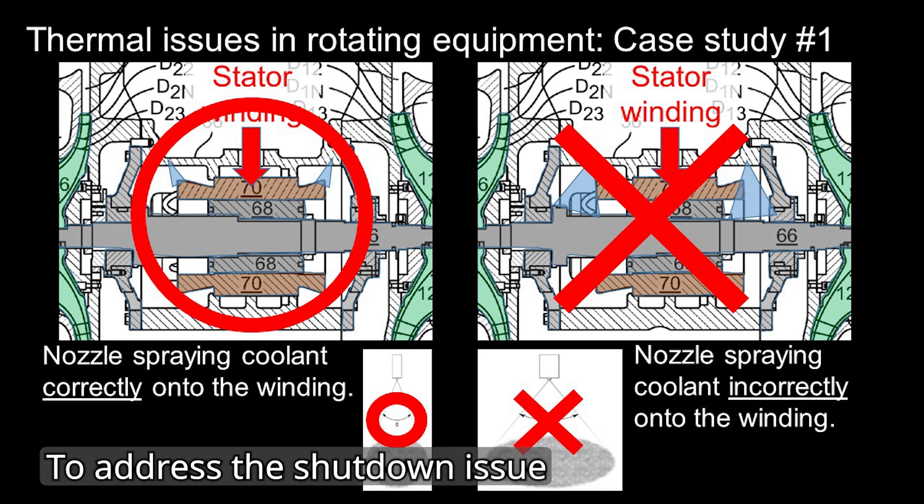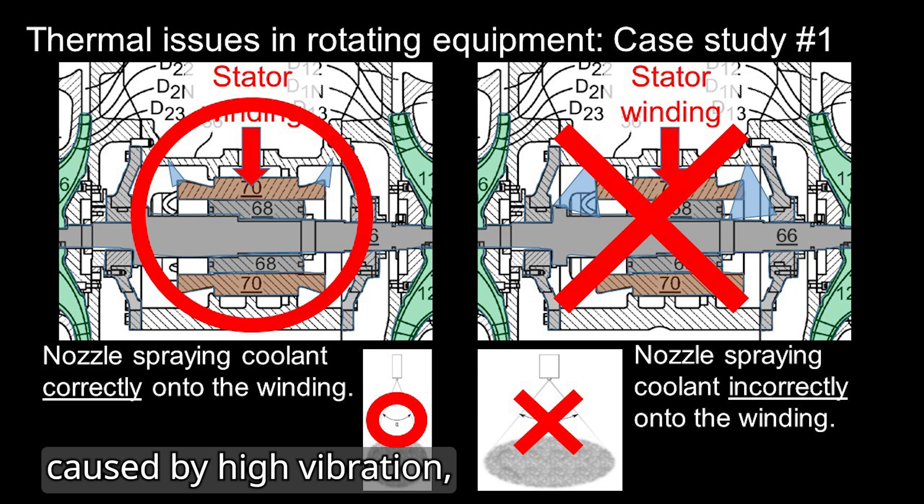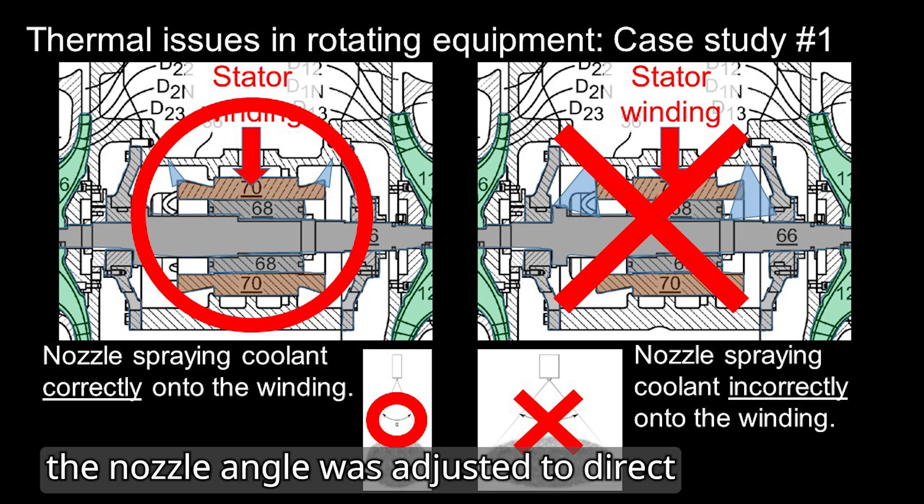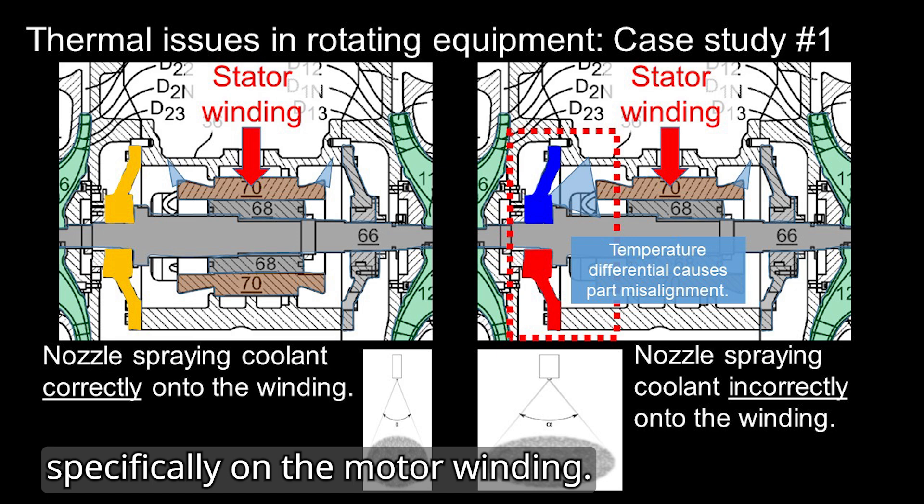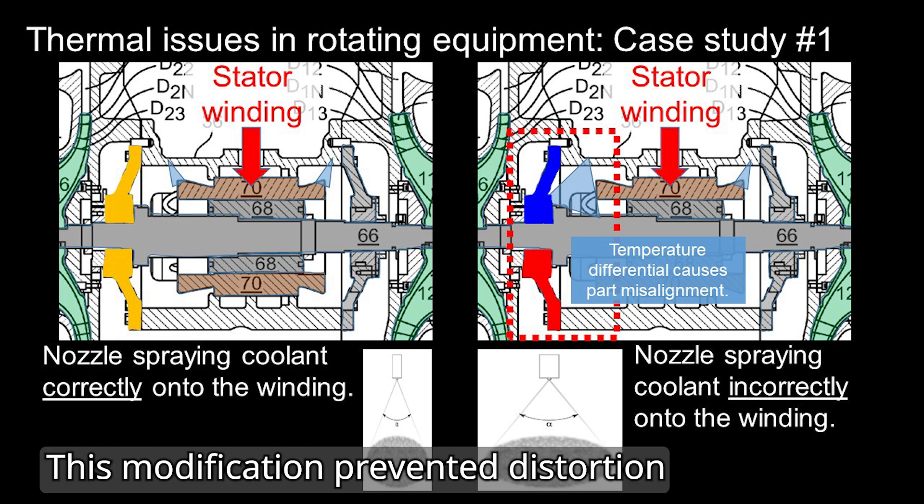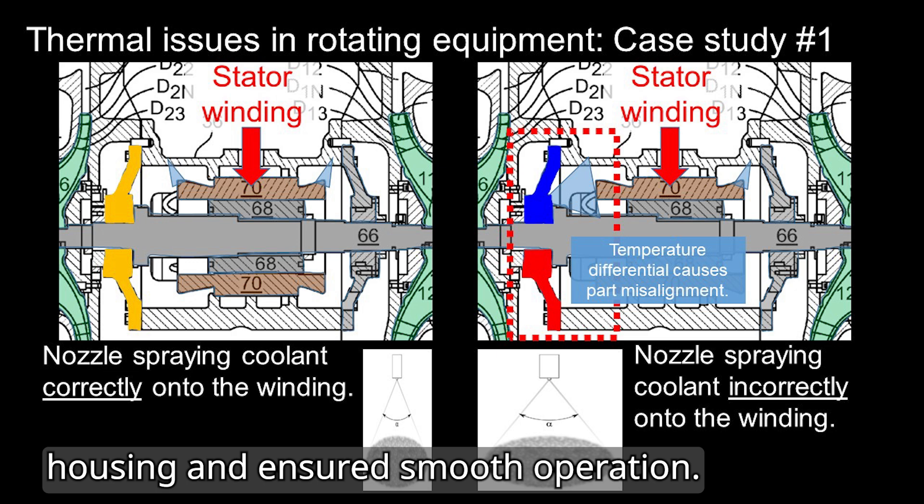To address the shutdown issue caused by high vibration, the nozzle angle was adjusted to direct cooling liquid flow specifically on the motor winding. This modification prevented distortion of the bearing housing and ensured smooth operation.